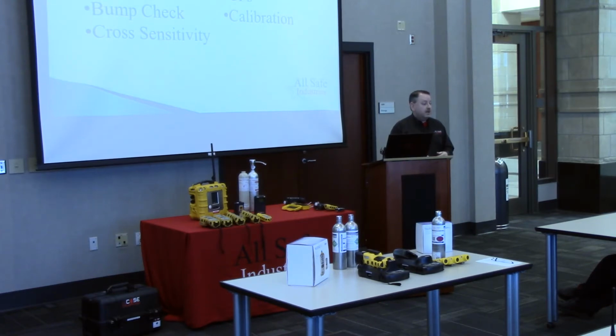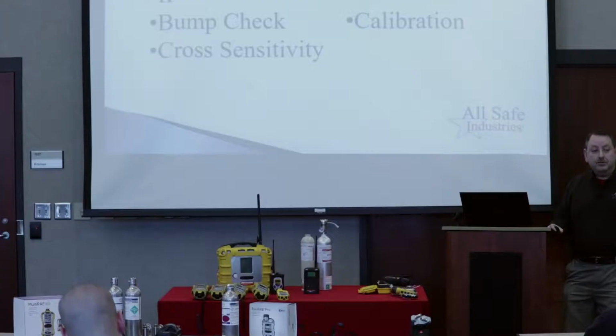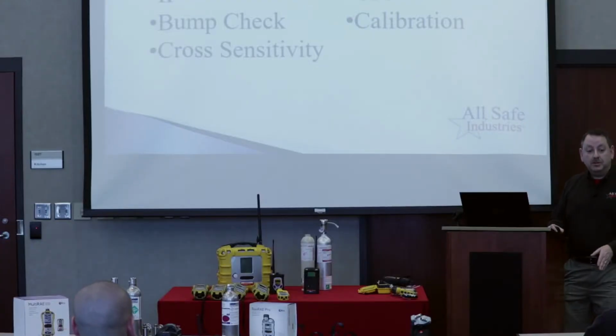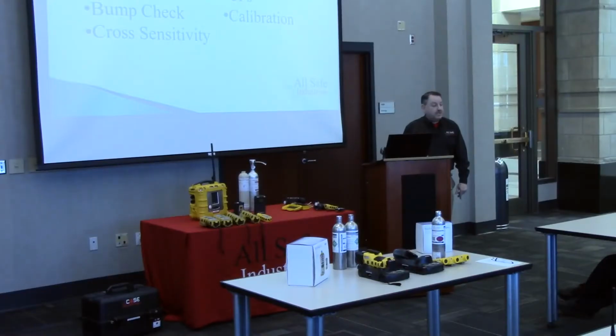So we'll talk about the difference between 4-gas meters and multi-gas instruments. One of the meters that you purchased is a multi-gas instrument. What makes yours different is that it's a 4-gas, but it also has an extra sensor that we'll talk about in a second. I mentioned flammable gases. We measure that with an LEL sensor. The acronym stands for Lower Explosive Limit.